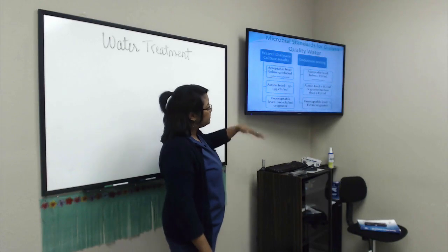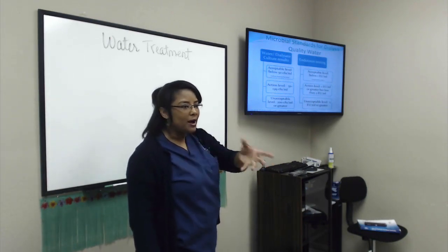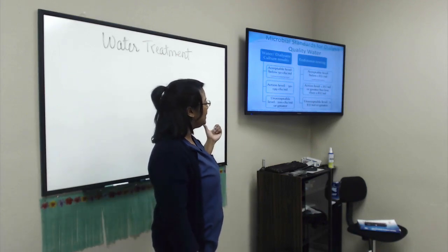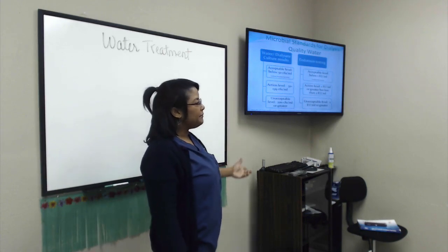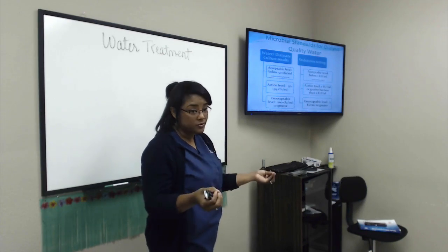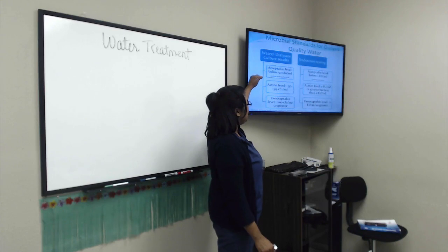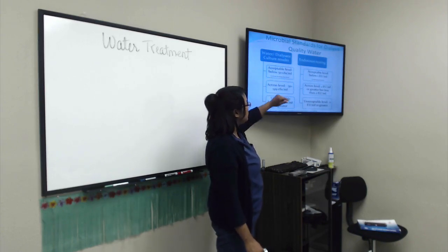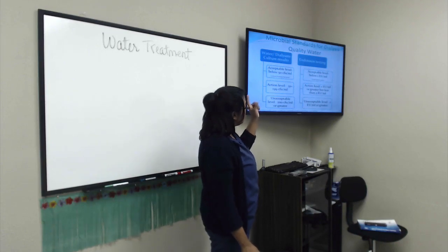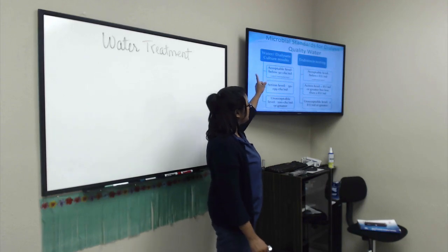And this is a test, a sample that is taken from the water and from the dialysate in a container, right? And then it's sent to the lab, and it's left there for a couple of days to see if something grows in it. So the acceptable level would be below 50 CFU, which means colony-forming bacteria, 50 CFU per ml. So that would be the acceptable level.